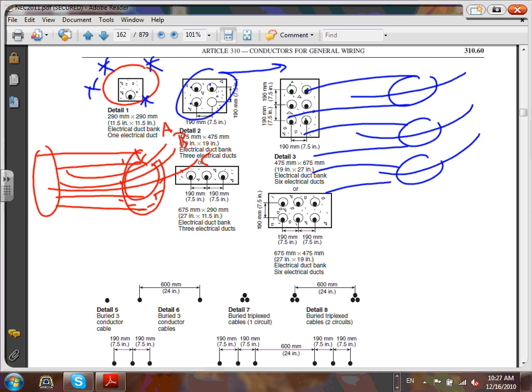I've actually done this. It was for machines that go from the hallway into a clean room build or area. So the ducts come up underneath the machine. That's all those multi-conductor cables. All the control is outside the room, so if you have to change out relays or whatever, you don't have to go into the clean room to do it. And they're like 3.